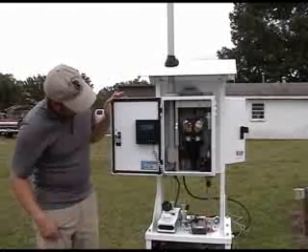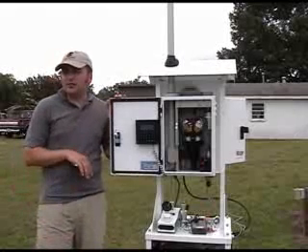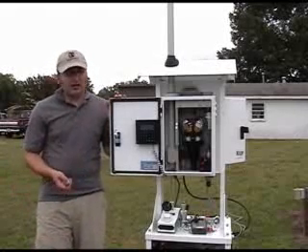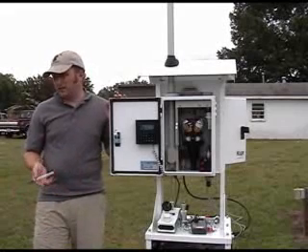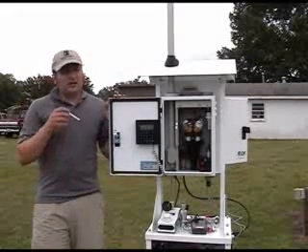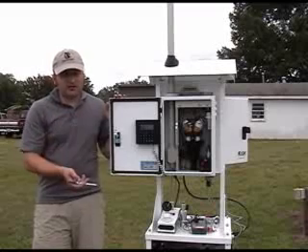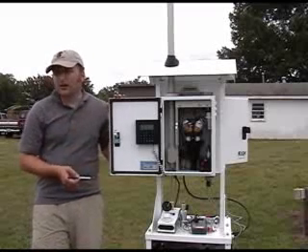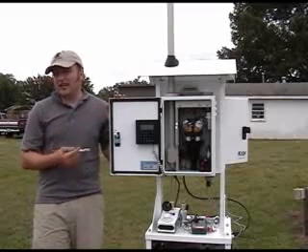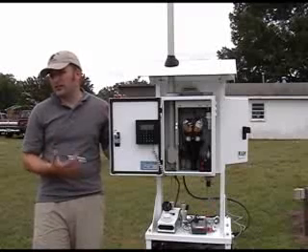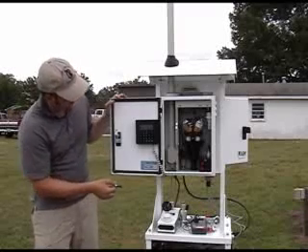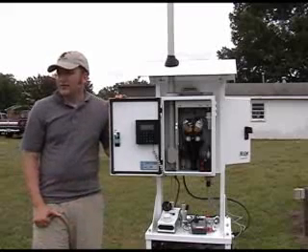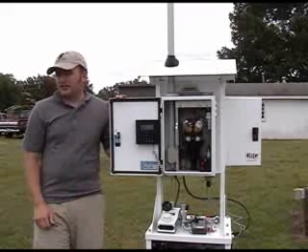F4 again. We can view the current elapsed time for the sample that's being run. Elapsed time is in minutes. Typically, a full sample day will be 1440. However, during the filter change process, the pump does come on, and there is sampling through the filter. The instrument does count that, so you can be as high as 1445, 1446 in your total elapsed time. But valid is plus or minus 1 hour? That's what the SOP says, yes. Okay.